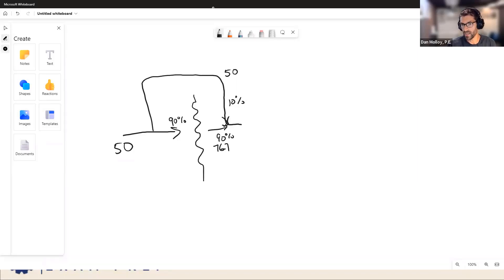So how would we do that? We would have to say, well, what was the CFM? 1000. That's a nice round number to work with. So we would say 900 CFM times 76.7 plus 100 CFM times 50, and then divide that by 1000. And that turns out to give you the same result as the way I approached it, which was using the coil efficiency formula.